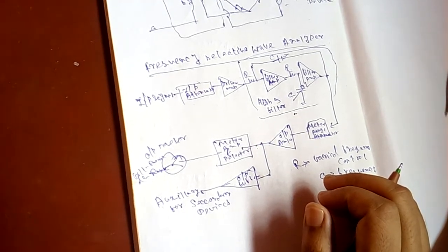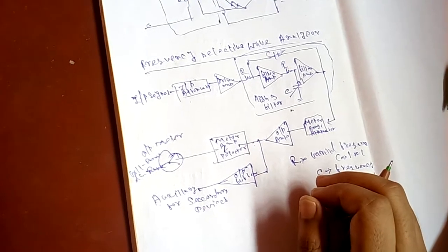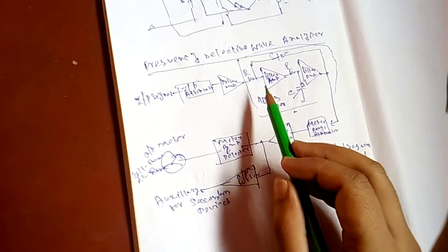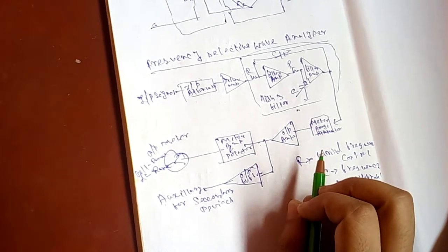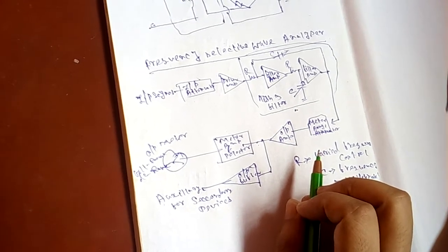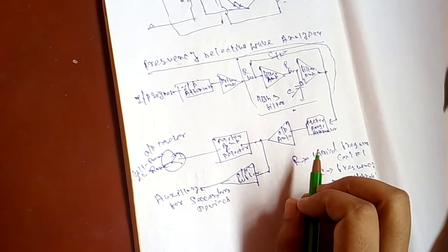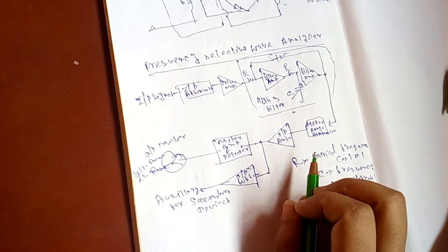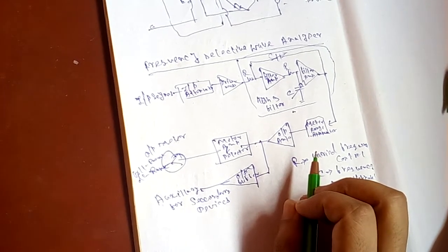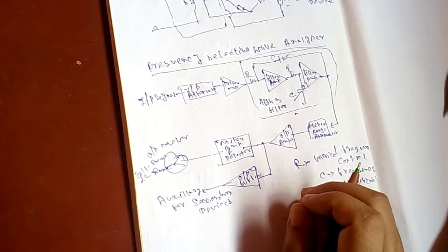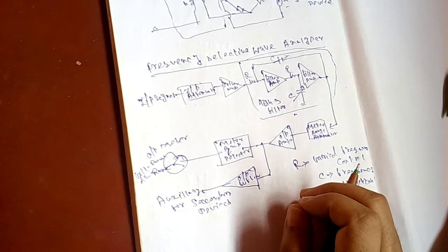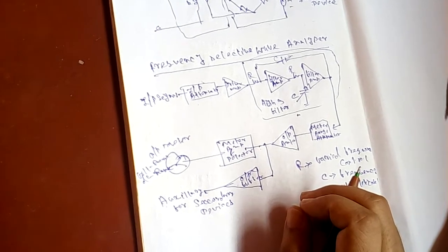The filter circuit consists of a cascaded RC resonance circuit and amplifier. We see the resistors and capacitors here, so it is an RC resonance circuit. For selecting the frequency range, close tolerance polystyrene capacitors and precision potentiometers are used for the resistance. The capacitors are used for range changing, and the potentiometer changes the frequency within the selected passband.